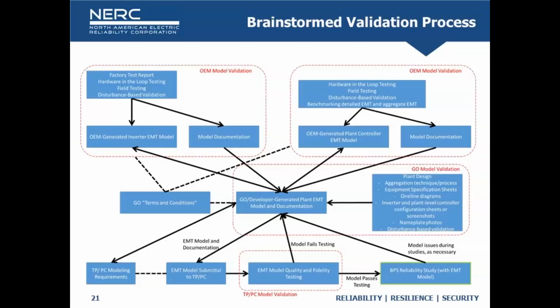So it's not just a model, it's model plus documentation. All of that goes to the generator owner or developer, who does some form of model validation and verification - looking at plant design, aggregation techniques, equipment spec sheets, one-line diagrams, plant-level controller configuration sheets, nameplate photos, all those kinds of things. That's really the accompanying documentation to say here's how I came up with a plant-level model that I feel is a reasonable check.